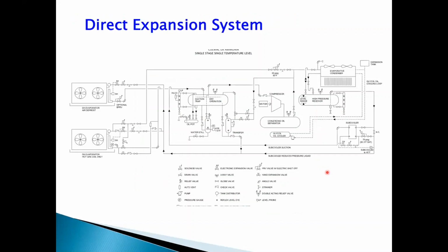So now you can have a multiple evaporator ammonia plant. If you see, most of the components, like compressor, oil separator, high pressure receiver, condenser, all remain the same. What we have here is an electronic expansion valve. It can also have a hot gas defrosting system, and this return is taken into one suction trap or suction accumulator, whatever you call it. It can also be used to separate the oil, and then the gas goes back to the refrigerator. So this kind of multiple DX systems are also now getting popular, particularly because of these electronic expansion valves.